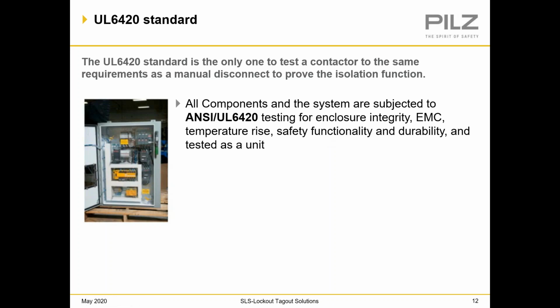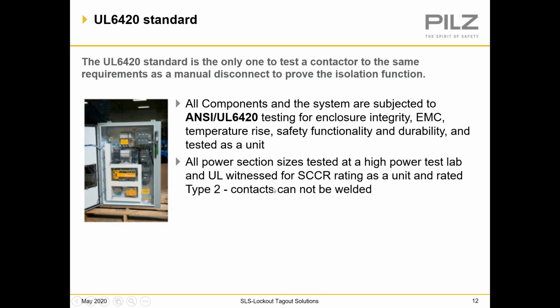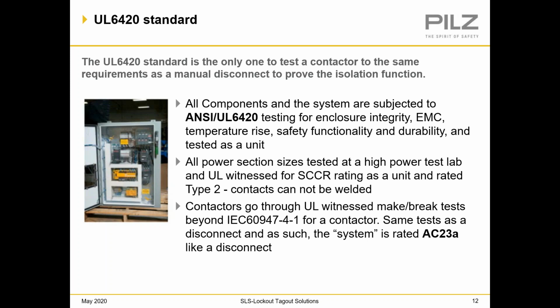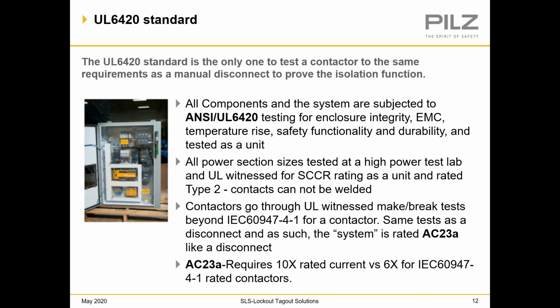All components and the system are subjected to 6420 testing for enclosure integrity, EMC, temperature rise, safety, functionality, and durability, and tested as a unit. All power sections are tested at high power test labs and UL witness for SCCR rating as a unit and rated type 2, and the contacts cannot be welded as previously where they can on the IEC standard. Contactors go through UL witness make-break testing beyond the IEC standard for a contactor, same testing as a disconnect, and as such, the system is rated AC23A like a disconnect. And with the AC23A rating, that requires 10 times the rated current versus 6 times the rated current on a general purpose IEC rated or standard contactor.